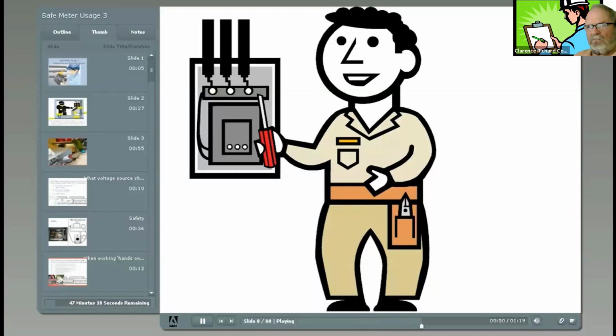This repairman was trained in the requirements of a lockout-tagout standard as an authorized employee. He was not, however, trained as a qualified person under the Electrical Safety-Related Work Practices Standard. The repairman was not adequately trained as a qualified person under the Electrical Safety-Related Work Practices Standard to perform lockout and tagout of electrical components. As a result, he could not have adequately verified that the circuit was de-energized.